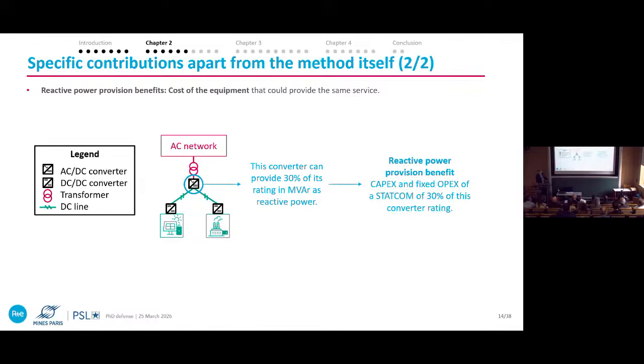So what I say is, as an hypothesis, but model driven by industrial data, 30% of a converter's rating in megawatt can provide its rating as reactive power. So reactive power provision benefit, at maximum, is a conservative approximation: the capex and fixed opex of a STATCOM of 30% of its converter rating in megawatt. So I consider reactive power provision being quite optimistic on the value it has by replacing STATCOMs.